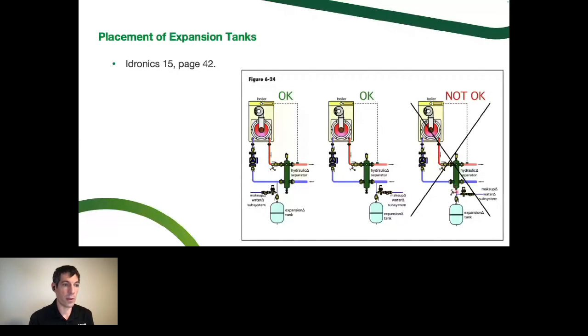So that would be a place that I would discourage, even though there is a nice tap there already. We see this quite a bit. Even if you put the expansion tank off to the side with a T or something, that would be a little bit better. But best case, we want to put it in one of these two locations, so we're not pushing that dirt that's been neatly separated to the bottom of the hydro separator anywhere, but staying right there until we have the opportunity to blow it down.